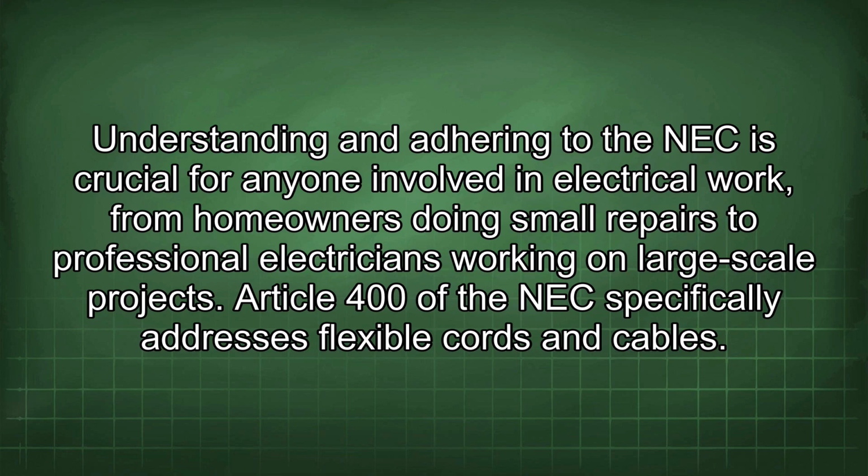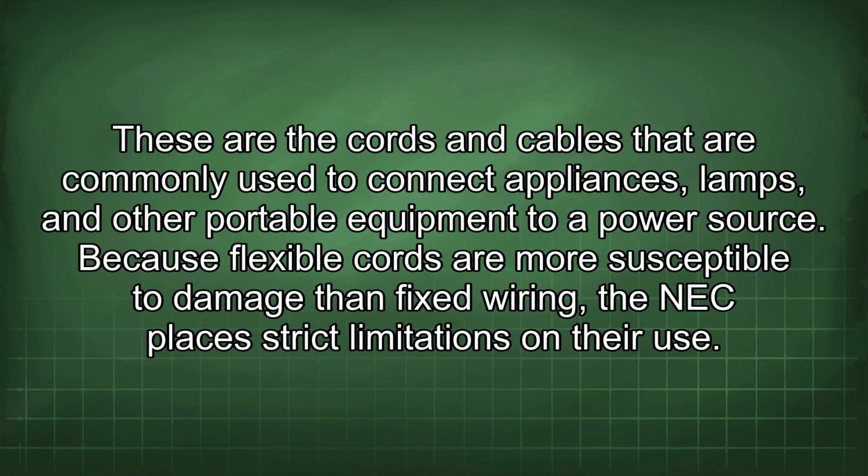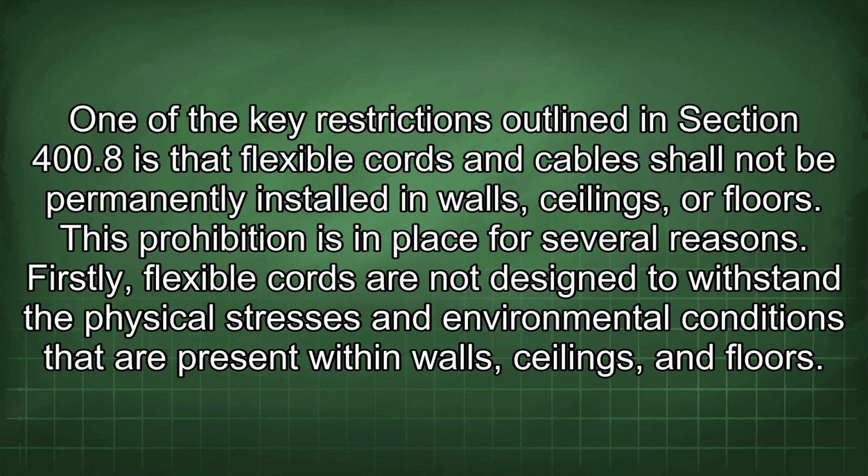Article 400 of the NEC specifically addresses flexible cords and cables. These are the cords and cables that are commonly used to connect appliances, lamps, and other portable equipment to a power source. Because flexible cords are more susceptible to damage than fixed wiring, the NEC places strict limitations on their use. One of the key restrictions outlined in Section 400.8 is that flexible cords and cables shall not be permanently installed in walls, ceilings, or floors.